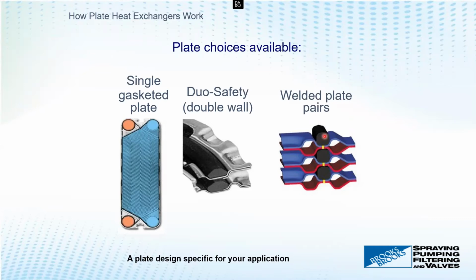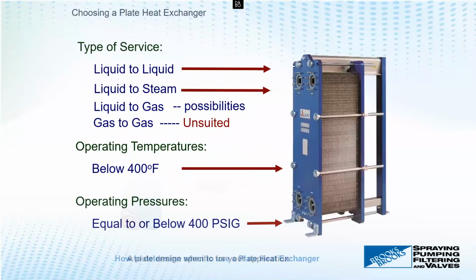And then you have the ability to actually maintain the outside by the gasketed plates. So you can take each plate pair apart, you can clean both sides on the outside, and then put it back together, so it's well maintained. This is actually quite commonly used in things like amine, ammonia, and some hydrocarbons. So those kinds of applications are common out there. So we're going to continue talking about the options you can get for plate pairs and inside your heat exchangers.